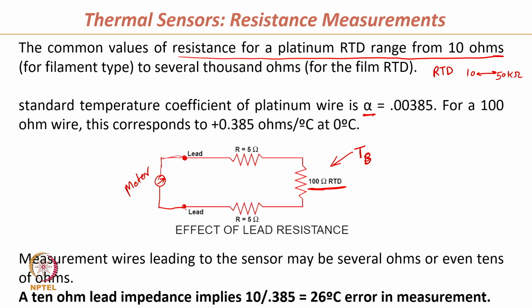this meter is connected to this RTD through these lead wires, these extension wires, these are called lead wires, which also has its own resistance. Let us say 5 ohm is the resistance of this one such lead wire. So, 5 ohm here and 5 ohm here. So, total is exactly 100 ohm of RTD plus 2 into 5 ohm because of the lead wire.